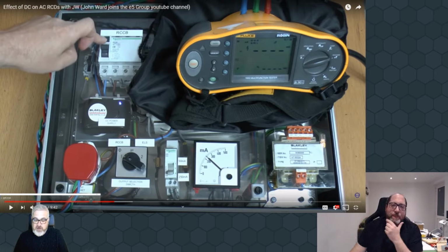Which was one of my bugbears, because when Amendment 3 came out it was like, right, now we're going to look at lighting circuits and all the rest of it. I had to write a risk assessment that exempted lighting circuits from RCD protection and just stick with the fundamental principles of overcurrent protection, mechanical protection. If a passenger could touch a luminaire, if it was broken, we would put an RCD in, but we had to use a special RCD manufactured to the old BS 4293 criteria, made by Blakley.